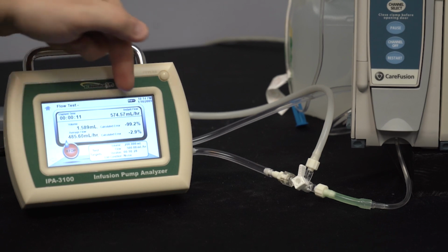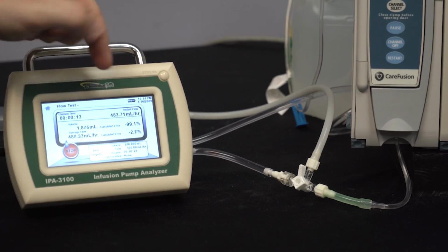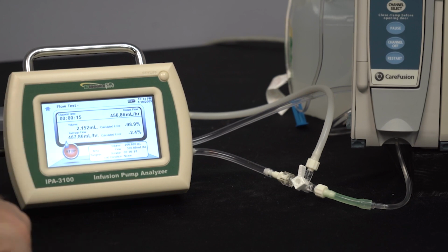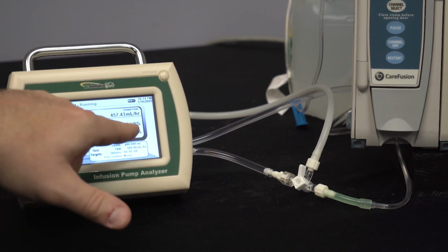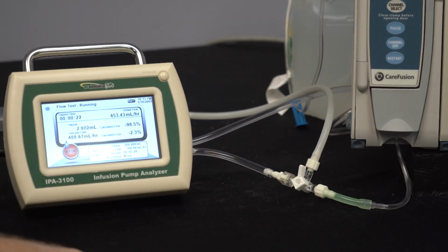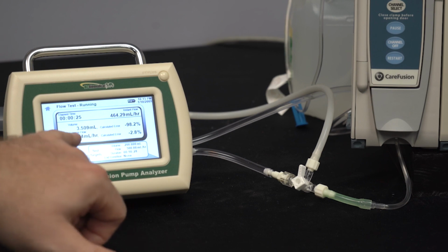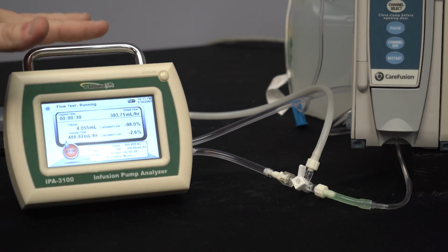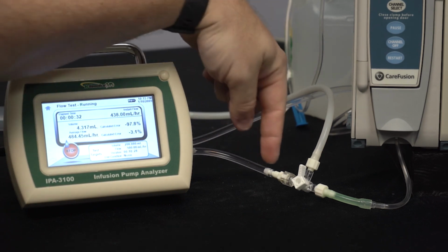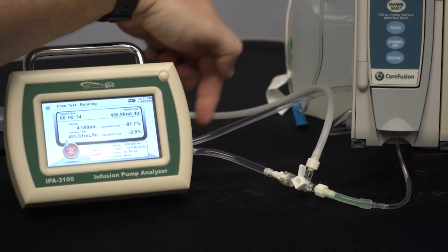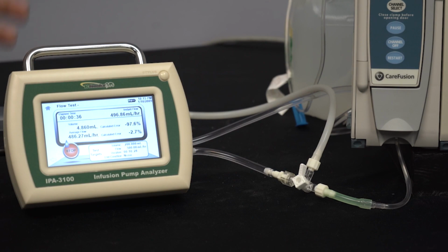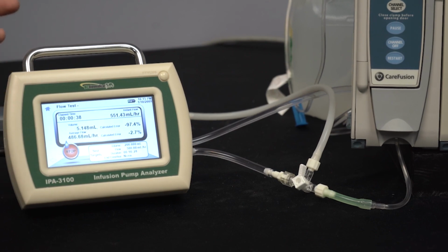We can see the instantaneous flow rate up in the top right, and our average flow rate over here. There's a large error for the measured volume, just because we haven't reached our target, and we're nowhere near our target, so of course there's a lot of error. Now, what's important is the test is running, it's stable, we've got a steady stream of fluid coming in, and we've got a steady stream of fluid coming out. So there's no air in the system right now.